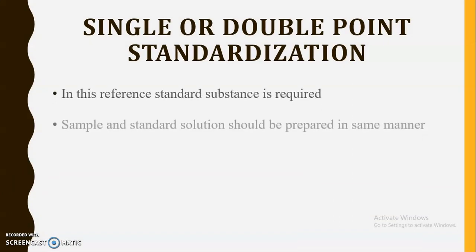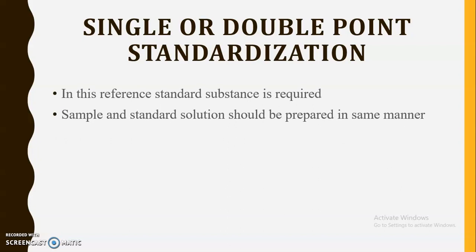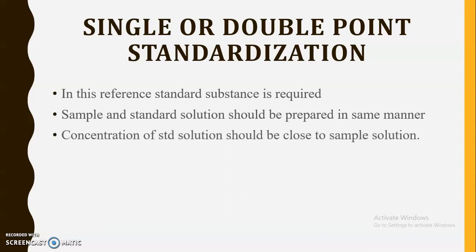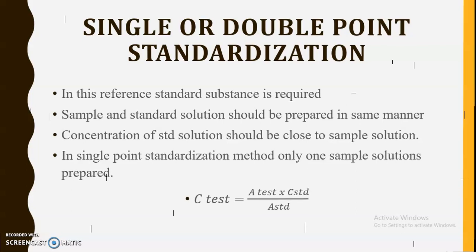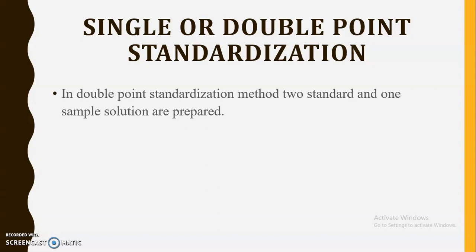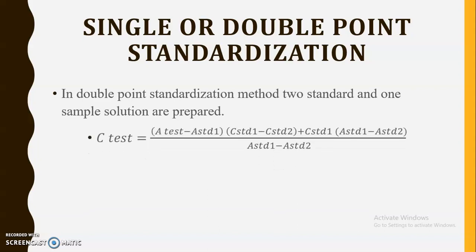The third method is single or double point standardization. A reference standard substance is required, and sample and standard solutions should be prepared in the same manner with concentrations close to each other. In single point standardization, only one standard solution is prepared, and concentration is determined as: C(test) = A(test) × C(standard) / A(standard). In double point standardization, two standards are used. These are the various applications of the UV visible spectrophotometer.